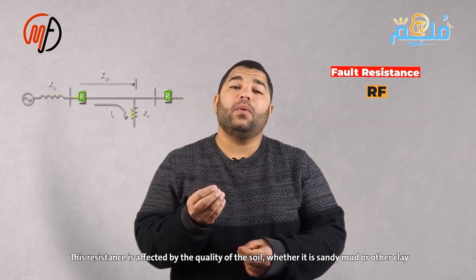Therefore, if we take into account the value of the fault resistance, the fault current can be expressed as follows: I fault equals V over Z line fault plus RF. This equation explains why it is difficult to detect faults with high resistance, as the increase in fault current is very slight.